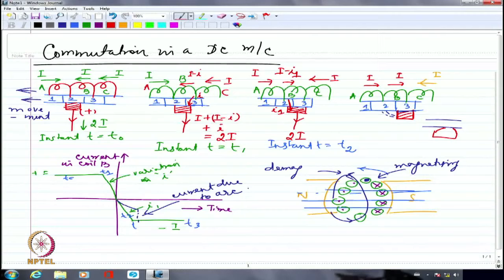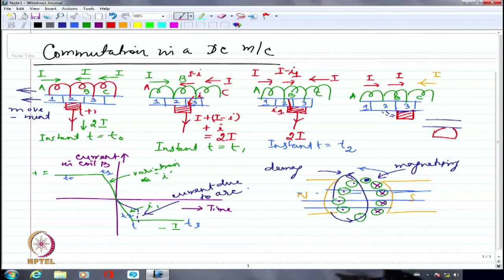This is one of the major problems with the DC machine — the commutator and brush arrangement causes continuous sparking, especially under load. This is a major reason why DC machines are never used in inflammable environments like petrochemical industries or mines, where combustible gases or flammable substances are present. Despite its many advantages, this commutation issue makes the DC machine disadvantageous in such settings.